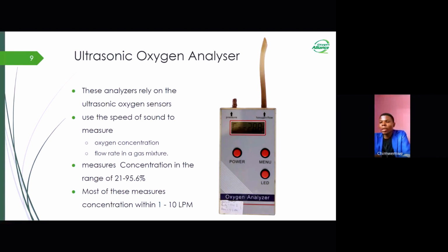So this will help us when we use these analyzers. It helps in ensuring patient safety and effective oxygen delivery. Most handheld analyzers offer portability for quick on-the-spot assessment of oxygen concentrators, and also anesthesia machines and ventilators. In addition, there is also an inclusion of pressure monitoring capability, which further enhances the utility of these oxygen analyzers and also maintains safety and effectiveness in oxygen delivery. This feature comes in handy mainly during maintenance and repair of the oxygen concentrator, just to make sure that we put back the concentrator at the pressure rated by the manufacturer.